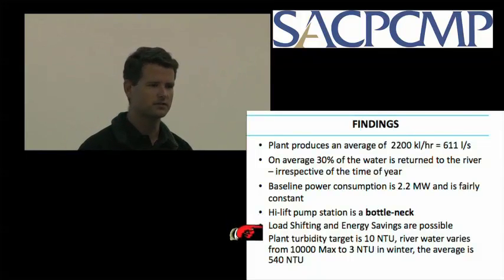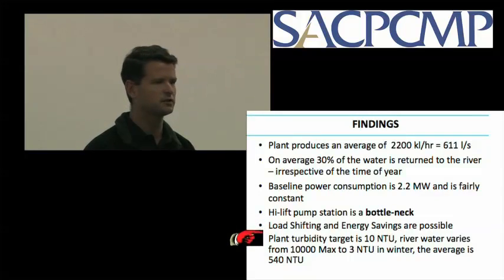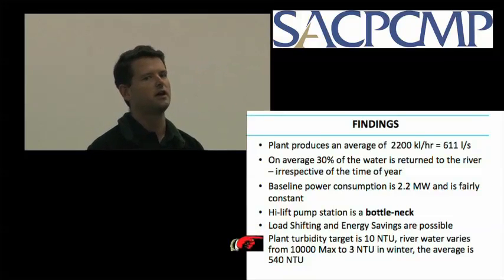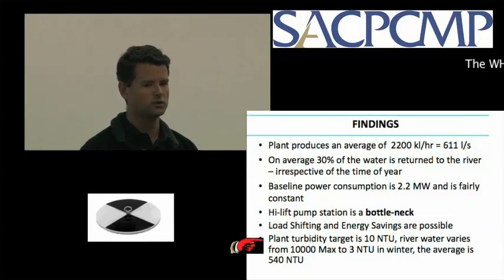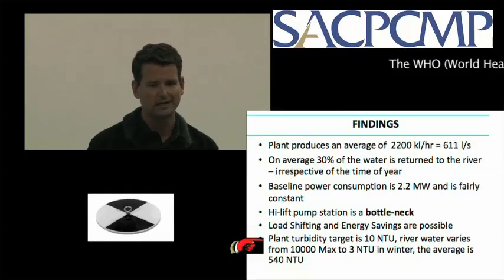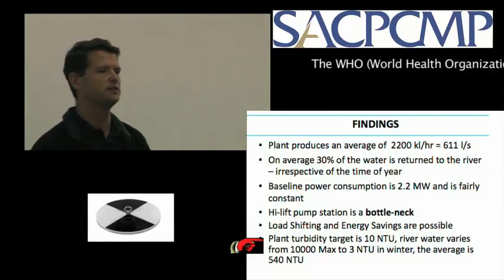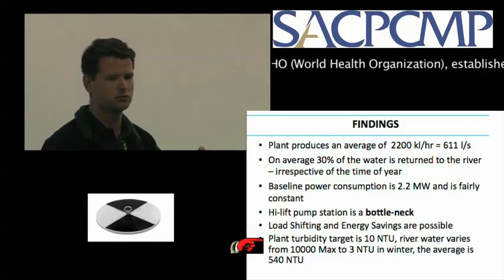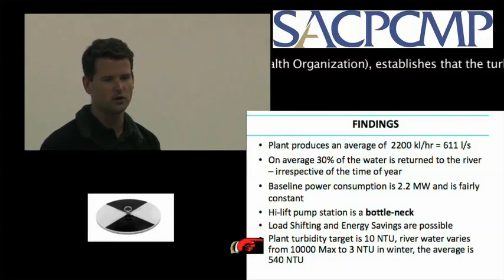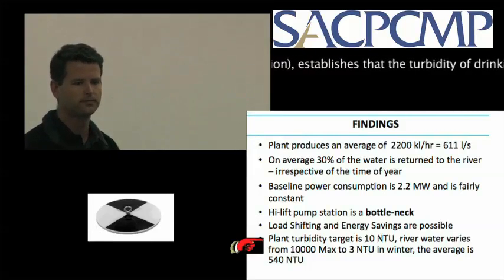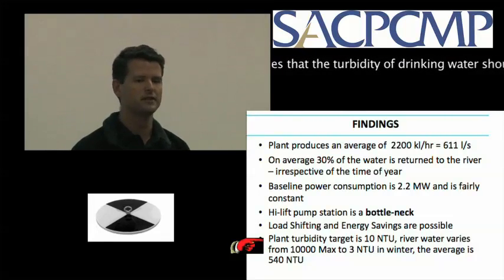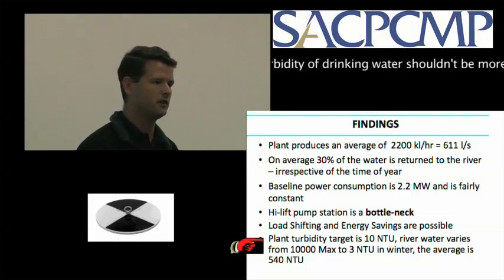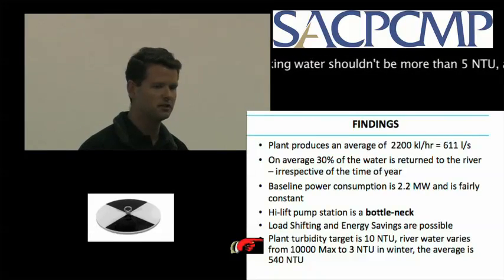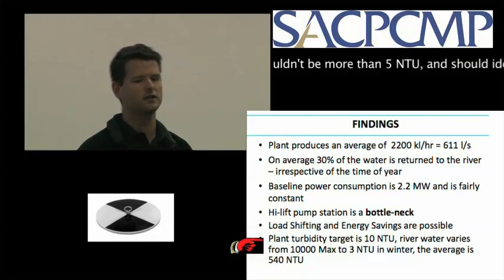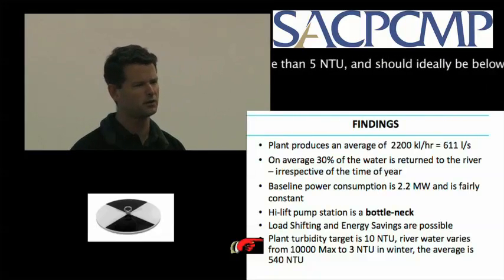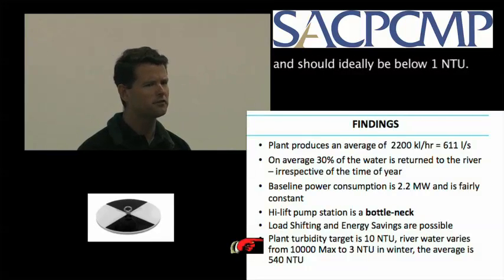One of the key sort of scary factors of this is if you're stopping this plant, how much can you process once you catch up, and what's the river plant turbidity doing? Now, the target of turbidity for the plant pumping out to the mill and to various other users was 10 NTU. The river water varied from 10,000 at the peak worst summer flood situation down to 3 in winter. So suddenly you see now, when you start looking at those trends, you say, well, in winter we've got a turbidity of 3 from the river.